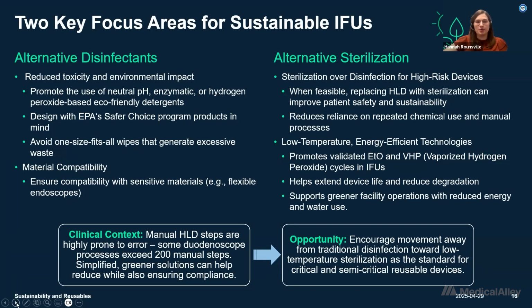Eco-friendly enzymatic or hydrogen peroxide-based detergents, which are biodegradable and break down into non-toxic byproducts when exposed to water and oxygen. We can take neutral pH products and formulations recognized by EPA's Safer Choice Program, which is a voluntary partnership initiative for disinfectant manufacturers aimed at promoting products with safer chemical ingredients, and also material compatibility matters. Sustainable solutions must still preserve device integrity through repeated reprocessing cycles. So by updating IFUs with recommending these alternatives, we reduce exposure to hazardous chemicals and support greener, safer clinical environments.